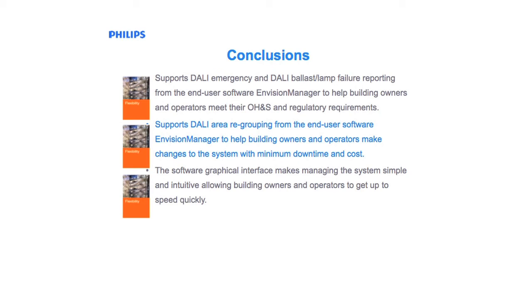Philips Dynalite supports full regrouping of the DALI universes through the head-end software. No additional cabling or network adjustment is required to the DALI controller as the system is completely configured through the Dynet network. The software package is completely graphical-based, allowing for easy use. A facility manager will be able to see the floor plan and where all the lamps are. There is no requirement for a working knowledge of the Dynalite system or how it is wired, as the software will manage all required settings.